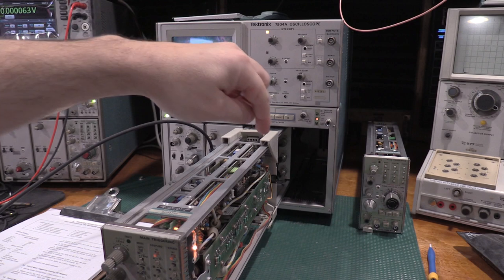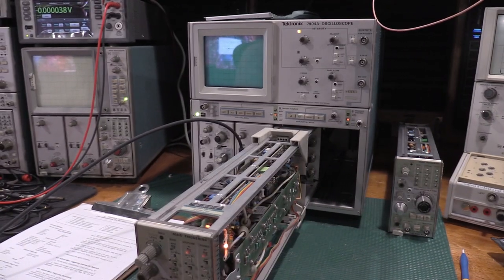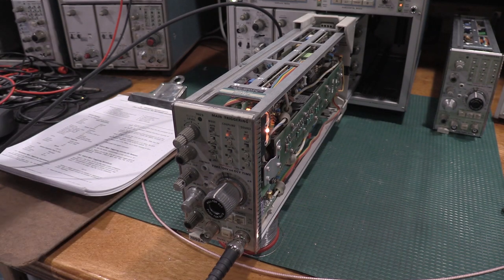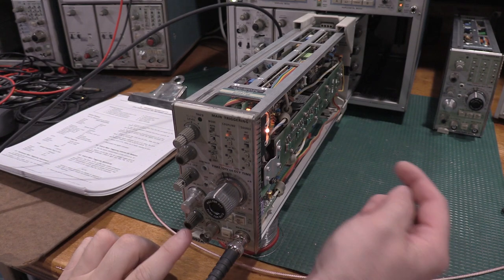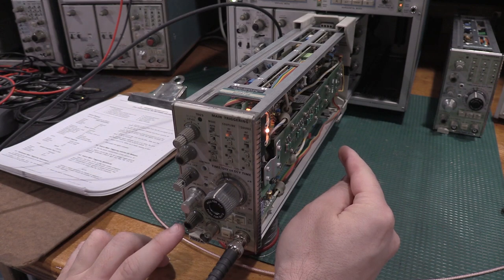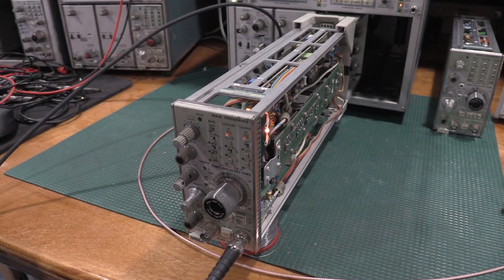The way you set up delay time centering is you hook the meter to the test points, then adjust the delay time to zero, and then adjust the pot for a meter reading of zero. I got it to 100 microvolts — 0.1 millivolts — which is close enough to zero for our purposes, especially for a device this old. The next step is to set the main triggering internal DC balance.